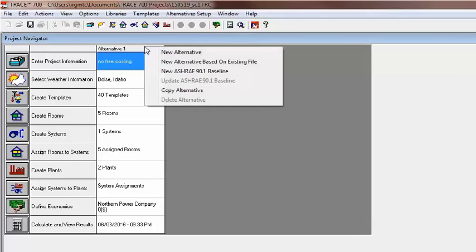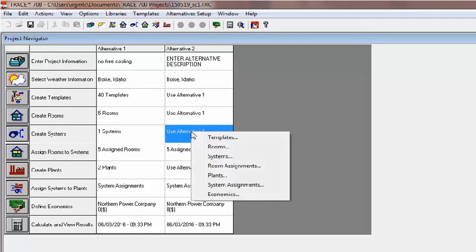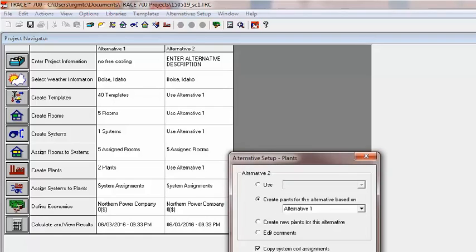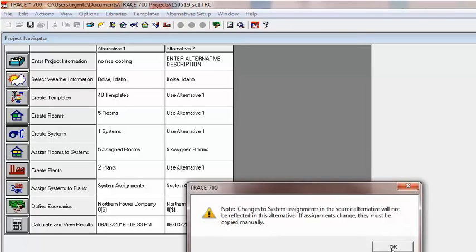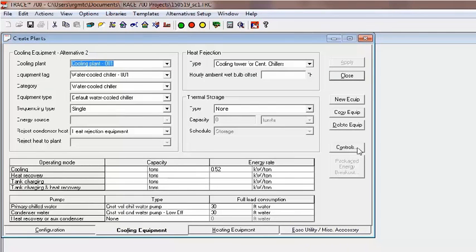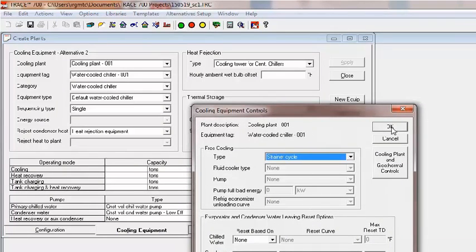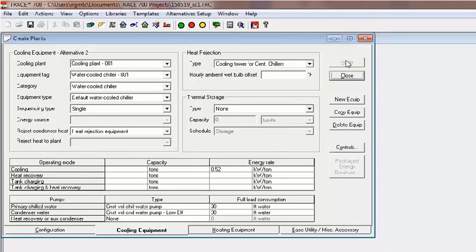Back in the Project Navigator screen, I'll copy the first alternative that we created with no free cooling. In order to determine savings, there must be a base alternative to compare to, as there is no specific report that reflects the savings from a waterside economizer. To modify the plant, right-click in Alternative 2, then select Plants > Create Plants based on Alternative 1, allowing modification of the plant input data. Then in Create Plants, on the Cooling Equipment tab, click on the Controls button. From here, I can apply Strainer Cycle to this plant. I hit OK, Apply, and it's done. It's not a bad idea to rename this alternative as well.